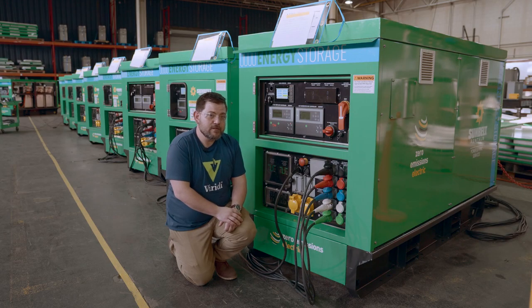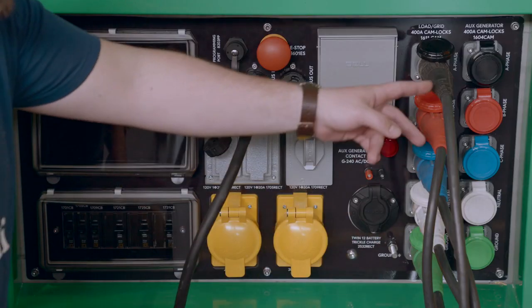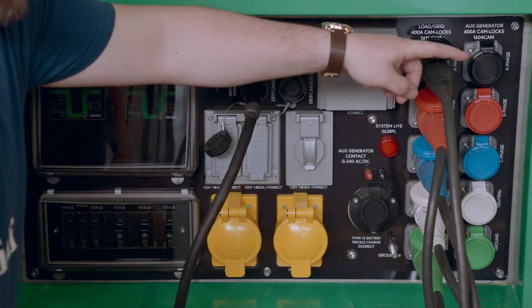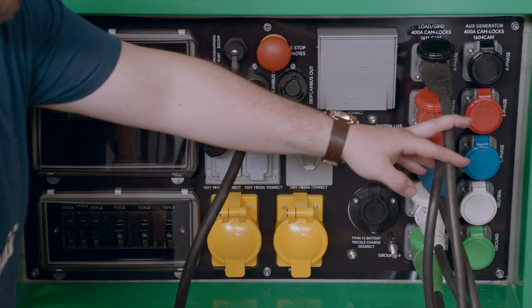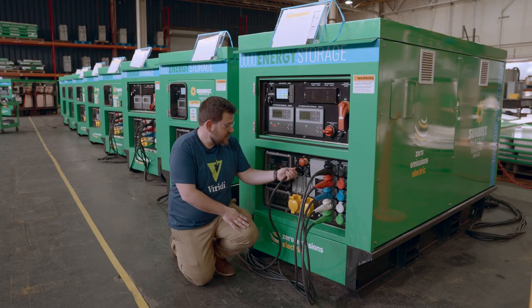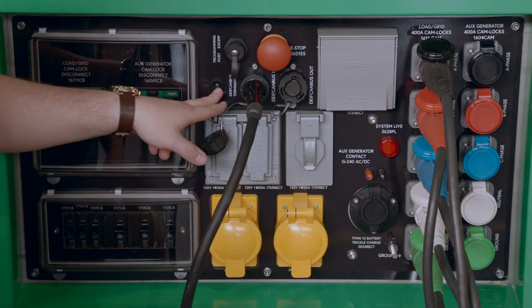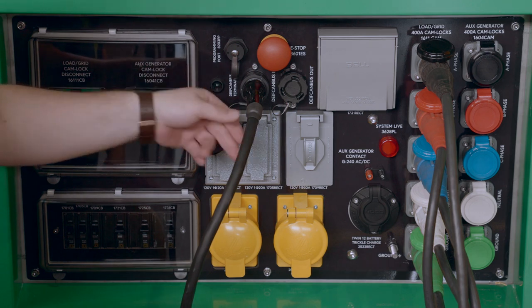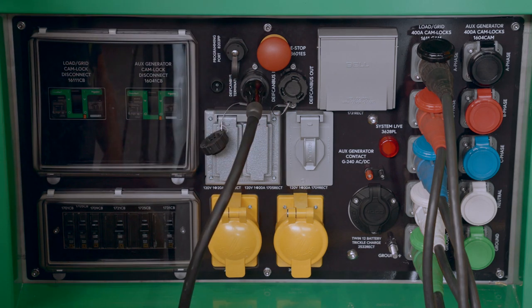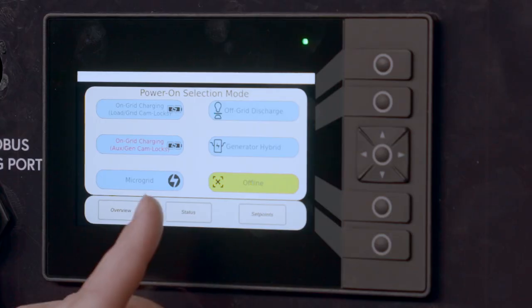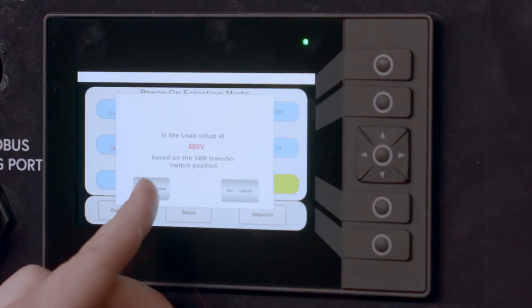The last operating mode I want to talk about is a paralleling mode, where we can actually parallel our units with similar units of our own or other paralleling generators. I'll go through the connection on one of our units. You'll see a brief scan of 4 units connected together. First, you'd hook up your cam locks from your load grid cam lock connections up to a bus or I-line panel. Next, you have your DIFE CAN bus cable, which daisy chains between your machines for CAN bus communication of the DIFE units. At the beginning and end of the run, you need to have the terminating resistor on to complete the circuit. At that point in time, you can then turn on your microgrid mode.